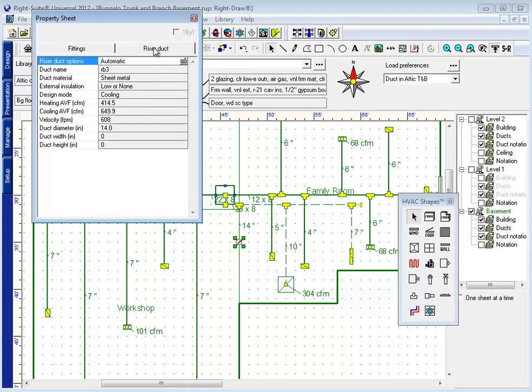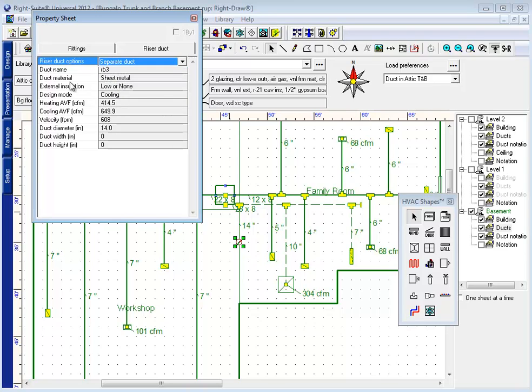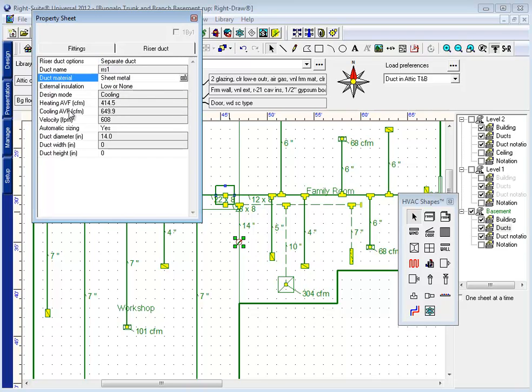In addition to that, I can make adjustments to the riser duct itself. And by default, it automatically calculates as simply part of the branch run. But I can change that to a separate piece of duct and size that duct as 3 inch wall stack.